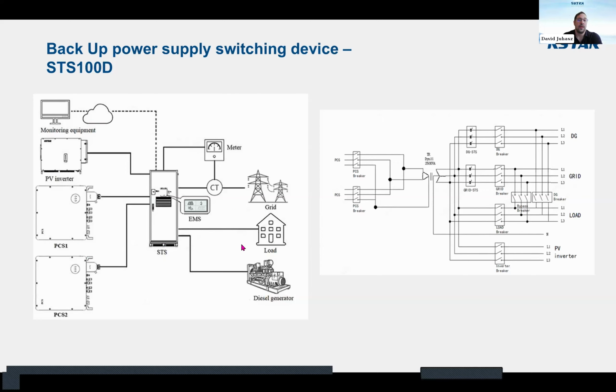And the other operating mode is the off-grid operation mode, when the STS is responsible for the switchover within 20 milliseconds to establish this ongoing power supply. And this is the main reason the STS needs to be installed, to protect the system, which needs to work during the off-grid.